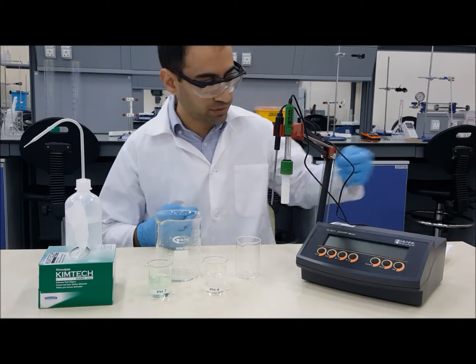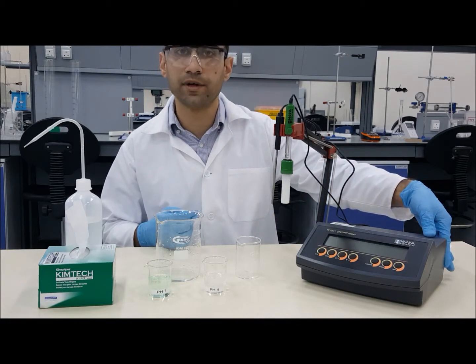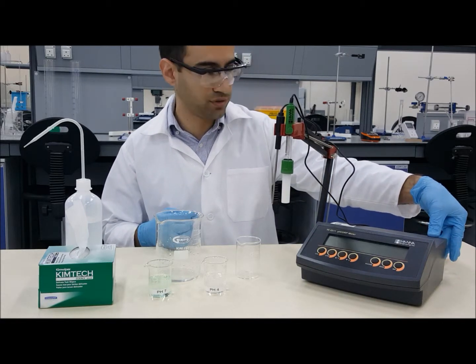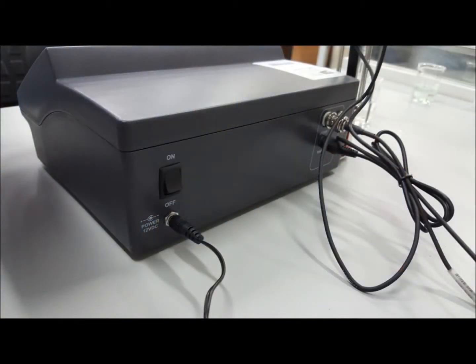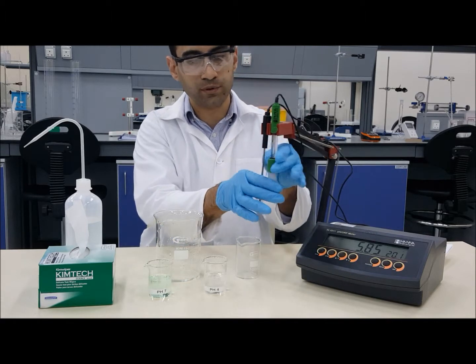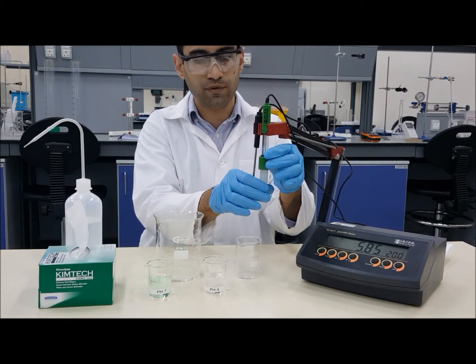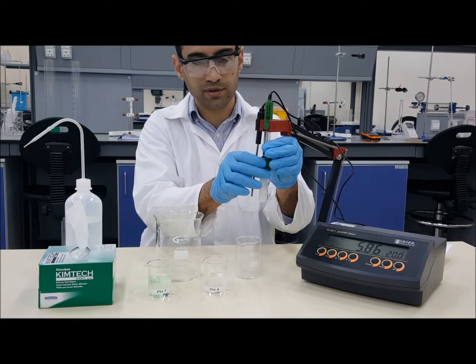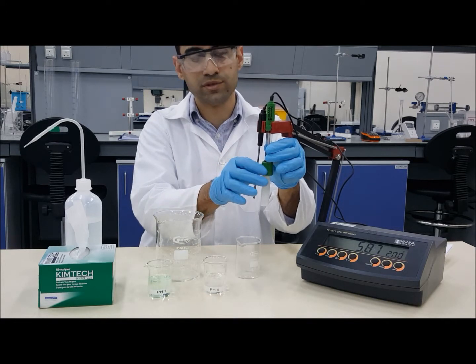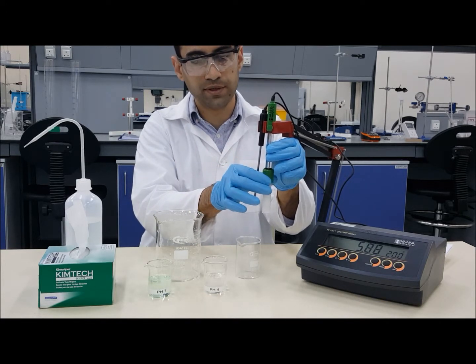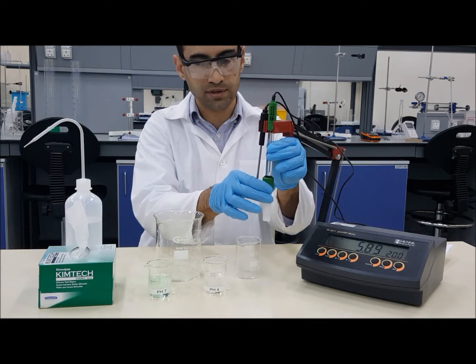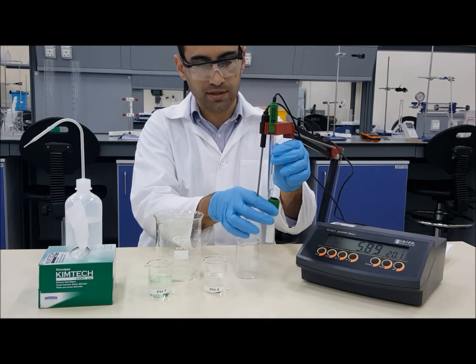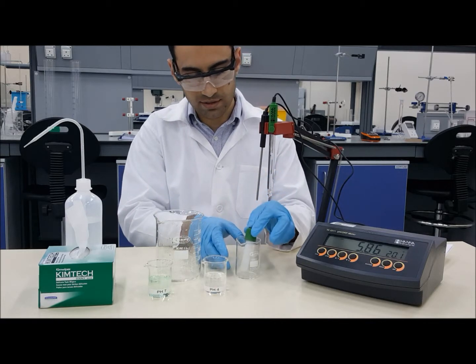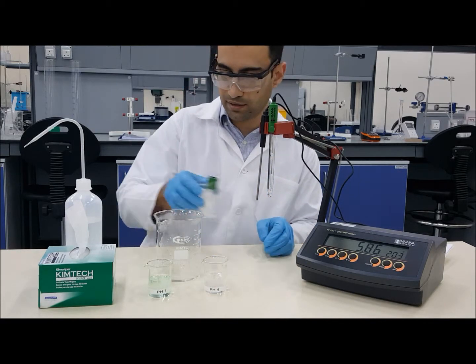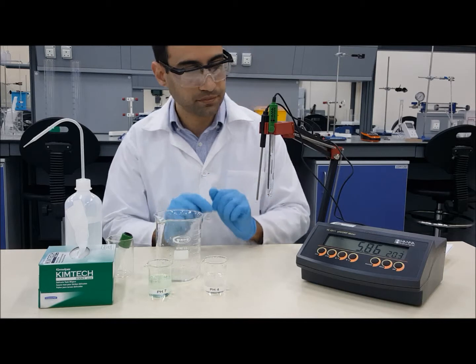To start with, you will need to switch on the pH meter from the on-off switch on the back side of the equipment. You will need to remove the protection cap from the electrode. Remember, there is buffer solution inside to protect the electrode, so be careful while pulling this out, and you can keep it in a beaker like so and keep it separately.